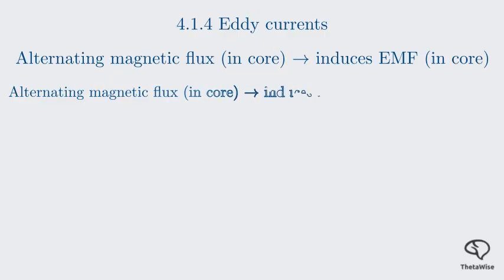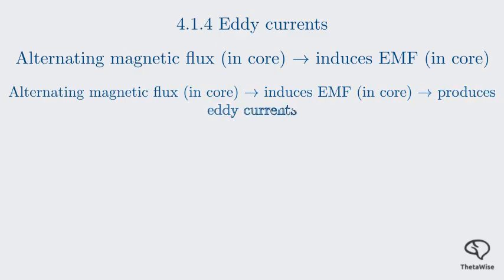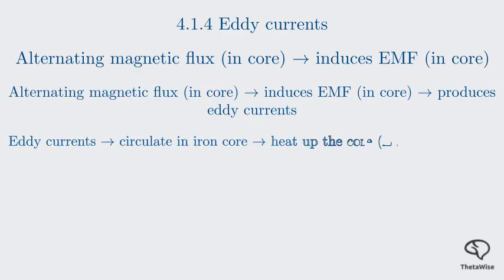These currents don't follow a winding. They circulate in closed loops within the core, much like eddies in a stream of water. They are known as eddy currents. As these eddy currents circulate, they encounter resistance in the core material. This resistance converts electrical energy into heat, causing the core to get hot. This heating represents wasted energy, which we call eddy current loss. It reduces the transformer's efficiency.